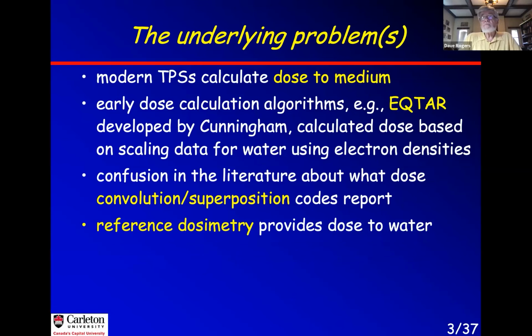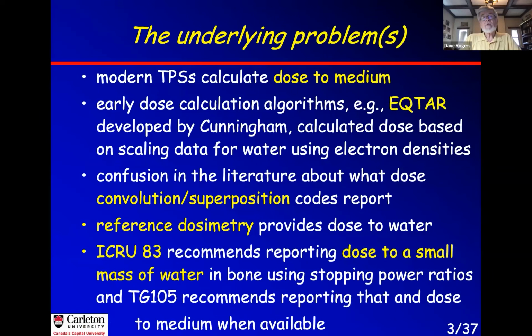Another reason that life gets complicated is that reference dosimetry, for example, TRS 398, provides the dose to water in the standard beam, so to speak, when you're calibrating your monitor units.